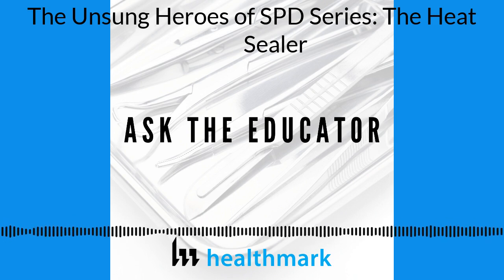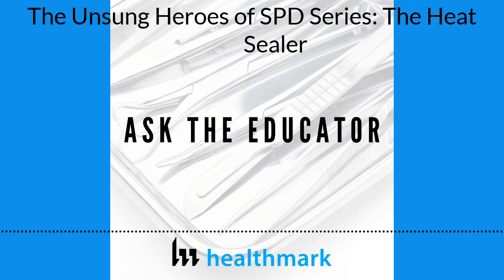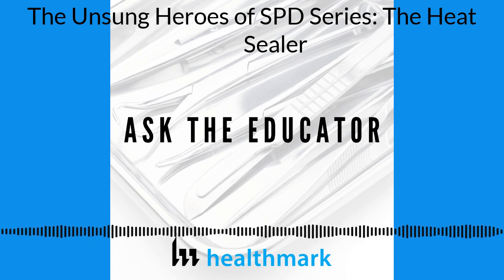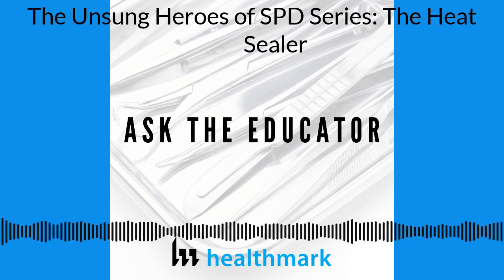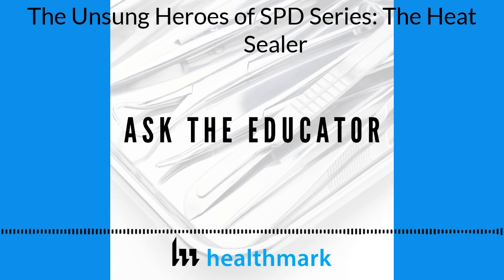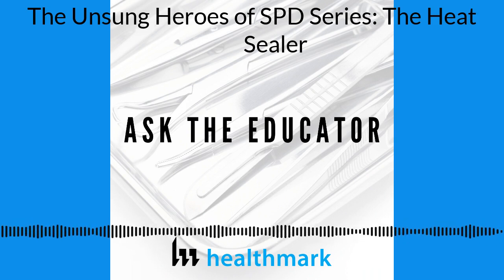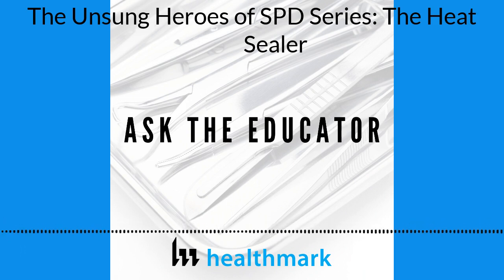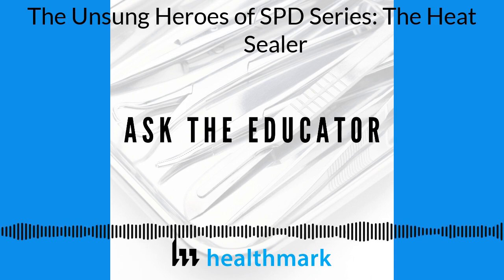And you can even go back to Joint Commission and look in the IC standards. I think it's 2.2.1, which requires the hospital to reduce risk of infections associated with medical equipment and devices. So here's a piece of equipment. You've got to seal pouches right. How do you make sure whichever one you're using is sealing properly? You test it every day. So you find the tests that you could do, and you record it and do it. I'm trying to show all the documents that say if you're not doing it, you really should. Will an auditor ask you? Probably not, unless you have some incident reports where you had failed pouches and sterility, and then you have to go back and do it.